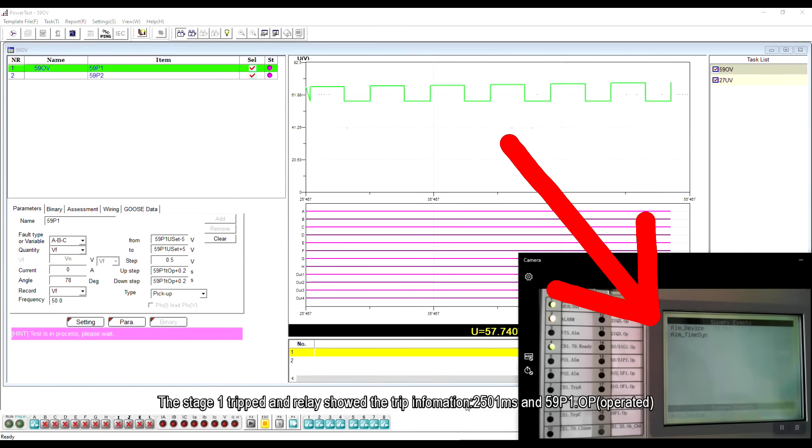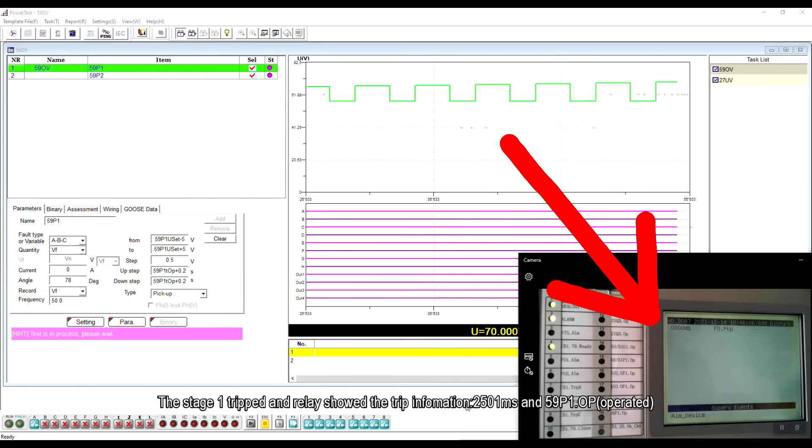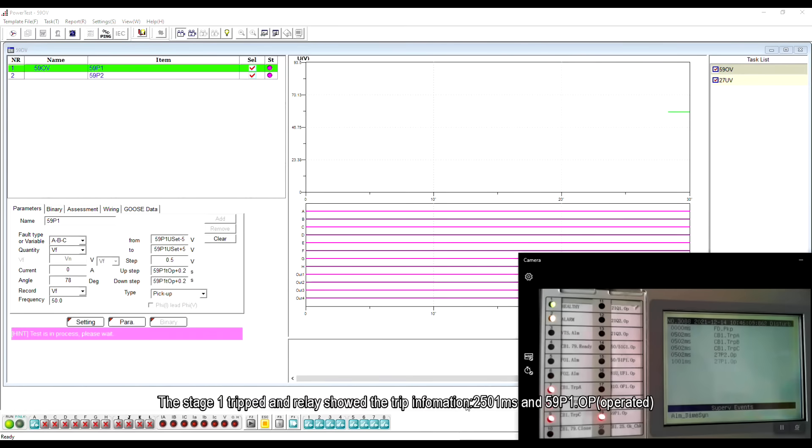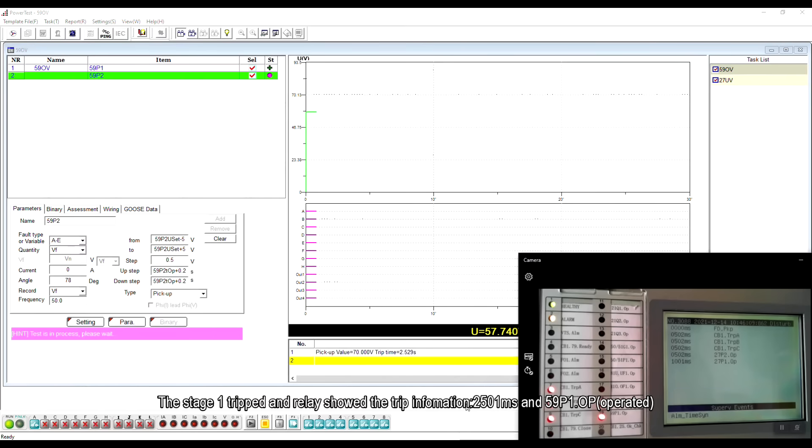The stage 1 tripped and the relay showed the trip information, 2501 milliseconds and 59P1 operated.